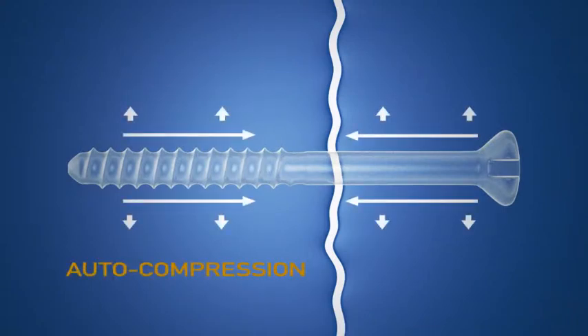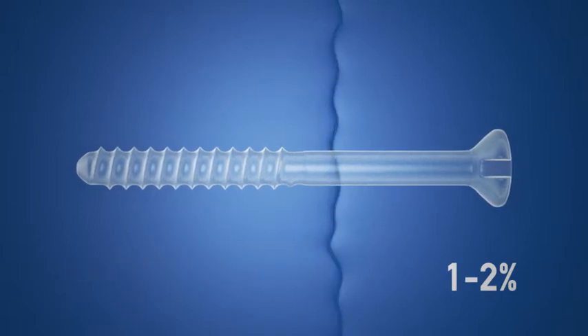Auto-compression involves lengthwise contraction of the screw by 1-2% and related expansion in the diameter. This memory effect based on mechanical activity both creates compression on the fracture line and prevents the screw from loosening as metal screws commonly do.